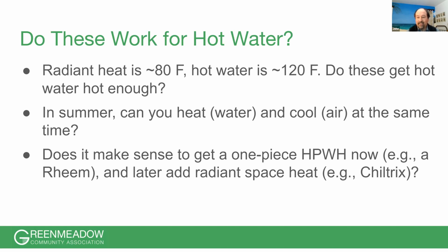So I just want people to understand that the heat pump tank type does take longer. That's why it's really important to have a larger tank so that you don't run out of hot water, and we're not pulling it all the way from 60 degrees back up to 120. We maybe shave it down to 90 degrees and then warm it back up to 120. So having a bigger tank does definitely help to maintain people's expectations for hot water. So that gets me back to your question. If you have an outdoor heat pump unit, it has a heck of a lot more horsepower to deliver the BTUs that people are going to expect.